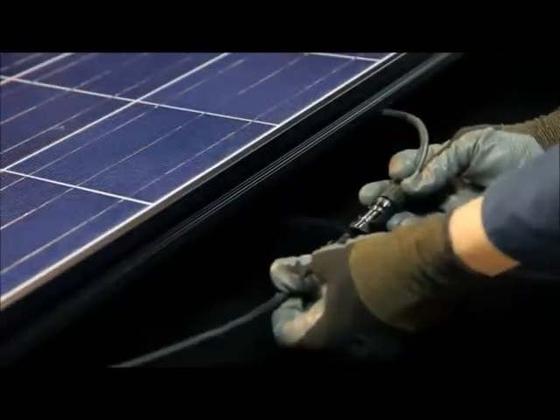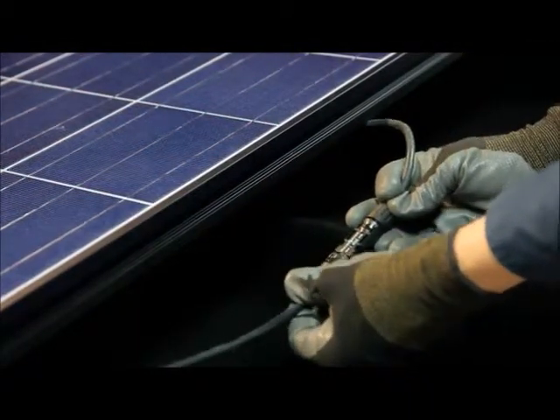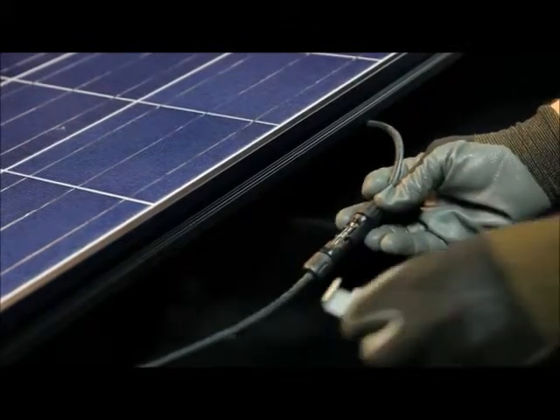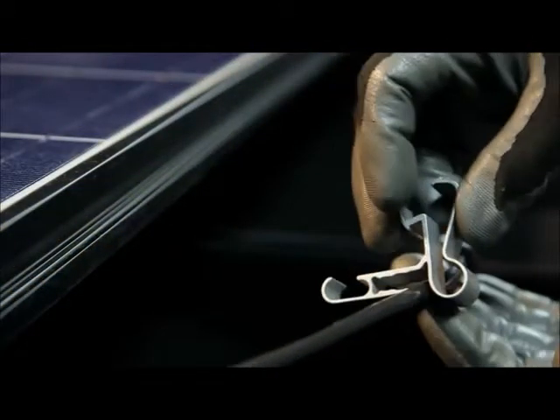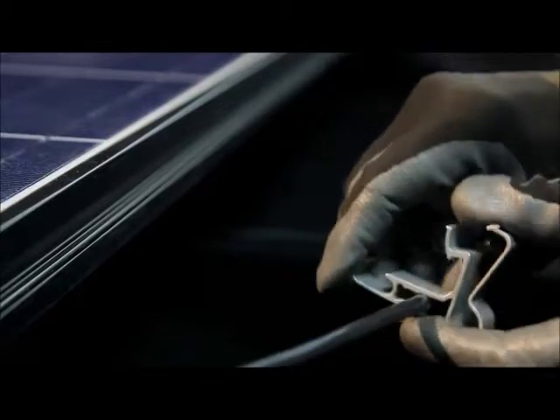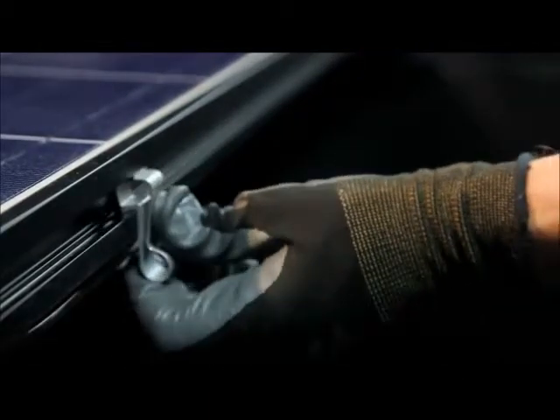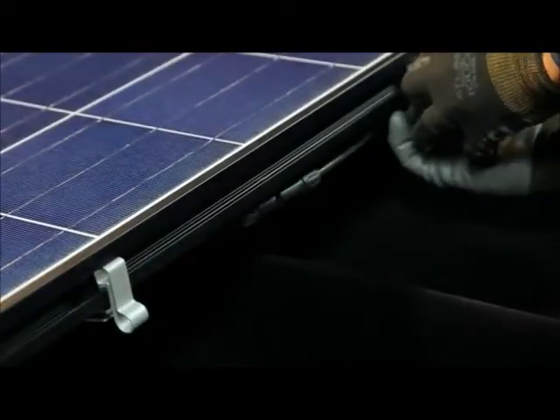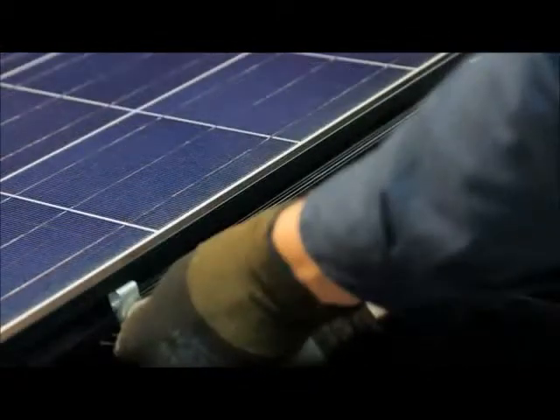The interarray wiring is managed on the up roof edge of the modules. To secure the wiring, load a cable into a cable clip and snap the clip into the groove. Slide the clip along the groove to eliminate cable slack. Two clips per module are recommended for proper wire management.